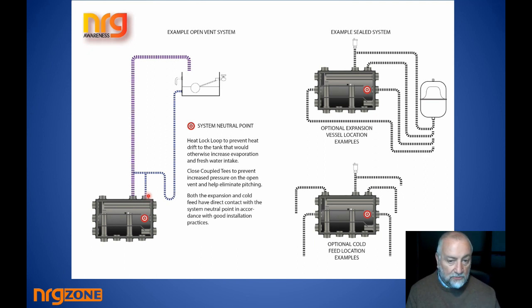I want to come to a very important point, and that is the cold feed connection to a heating tank. 99% plus of the time you find they're brought down and they're brought directly onto the top of a pipe or top of a connection, and then that allows the heat to drift up the cold feed pipe and form a one pipe circulation. By that I mean the water touching the wall of the pipe will be cooler and start to tumble. The water going up the middle of the pipe will form a circuit, and it'll tumble within itself, within the pipe, upwards till it reaches the tank.